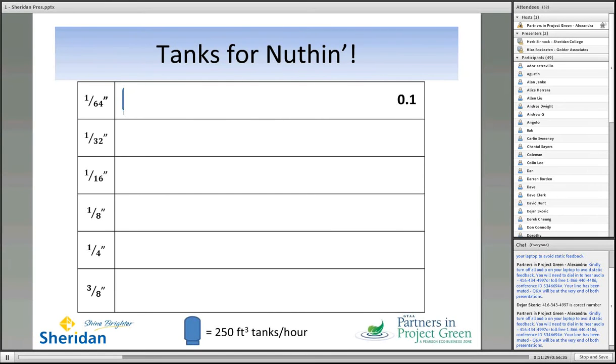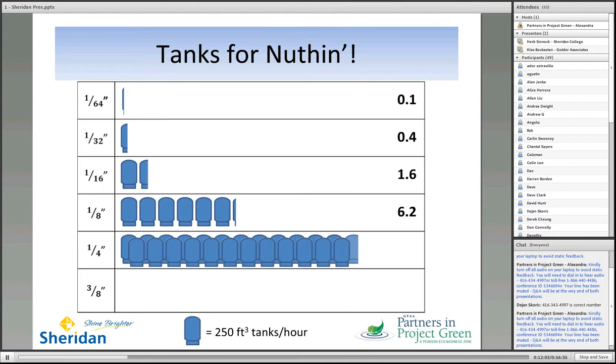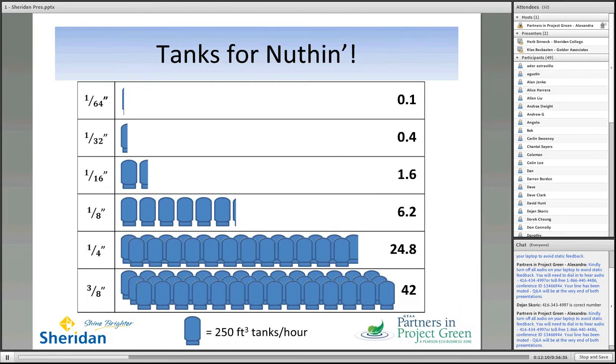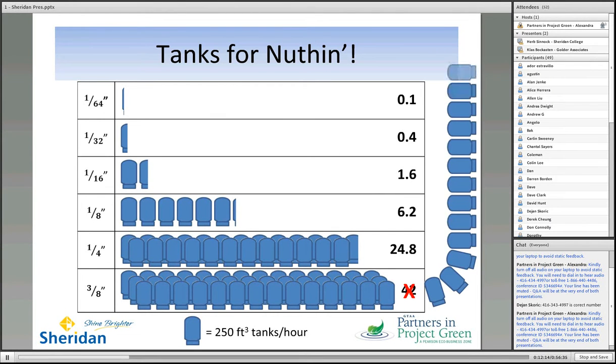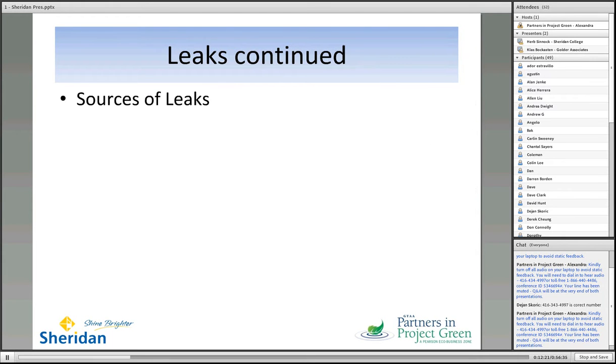To give you a little more perspective on the CFMs, we tried a little graphic here using a tank of 250 cubic feet, which is essentially like a 10-foot high tank with about a 5.5-foot diameter. It's fairly big, a standard size, but a big receiver tank. And we wanted to convey to you how much of that tank's capacity would be used feeding leaks of various sizes. So a 1/64-inch leak is using only about 1/10 of that, but as you get up towards a 1/8-inch size leak, it's about 6 tanks per hour. And as you get even bigger on leaks, or you go towards open blowing at 3/8 of an inch, you can quickly see that so much of that capacity is being fed to the leak. This is not something we want.